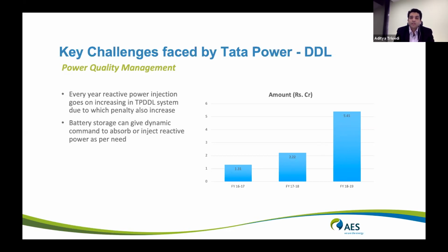And the way the system works is that the full 10 megawatt capacity can actually be used as reactive power. So that 10 megawatt of reactive power can be injected onto the grid. It's not just energy; both active and reactive power can be managed. That's another application which Tata Power is testing in this asset. The results are awaited, and we'll share some experiences in future.